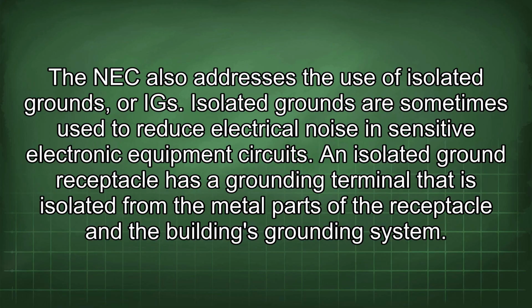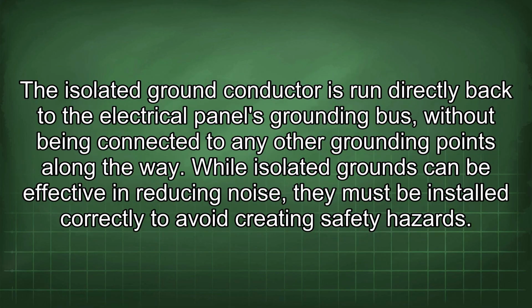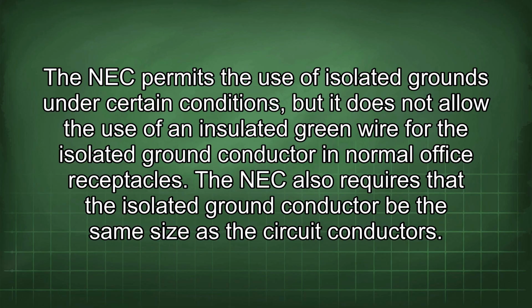Isolated grounds are sometimes used to reduce electrical noise in sensitive electronic equipment circuits. An isolated ground receptacle has a grounding terminal that is isolated from the metal parts of the receptacle and the building's grounding system. The isolated ground conductor is run directly back to the electrical panel's grounding bus, without being connected to any other grounding points along the way. While isolated grounds can be effective in reducing noise, they must be installed correctly to avoid creating safety hazards. The NEC permits the use of isolated grounds under certain conditions, but it does not allow the use of an insulated green wire for the isolated ground conductor in normal office receptacles. The NEC also requires that the isolated ground conductor be the same size as the circuit conductors.